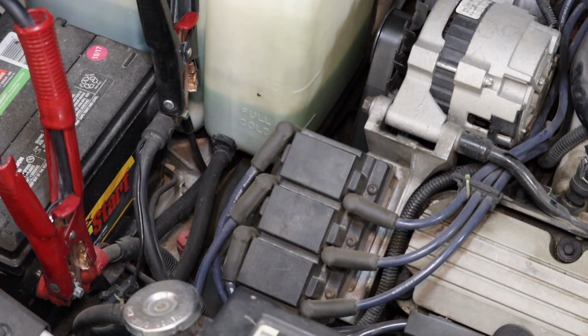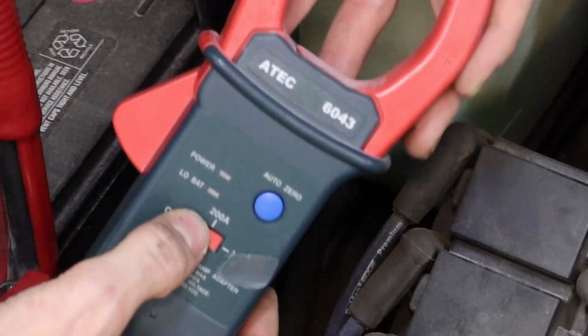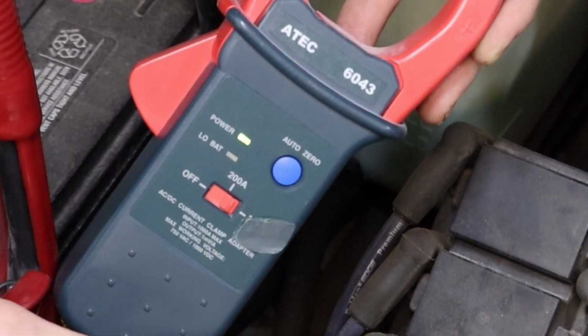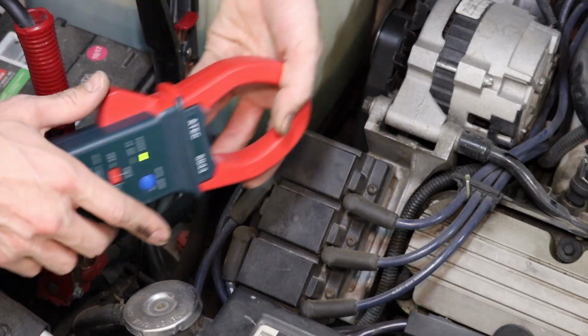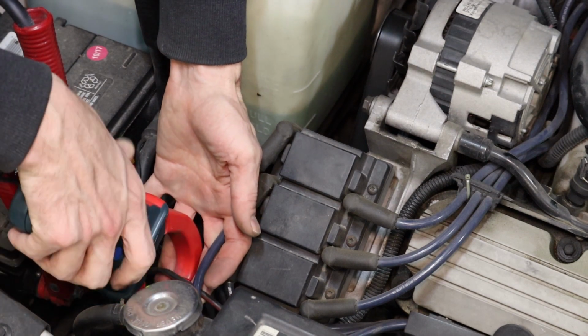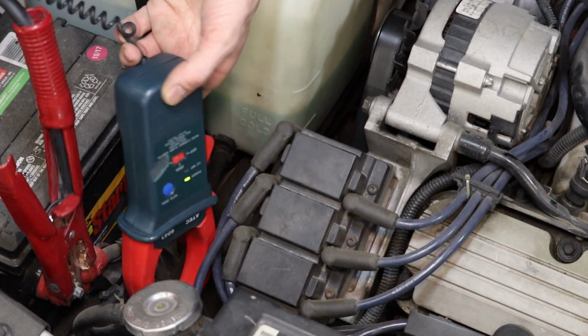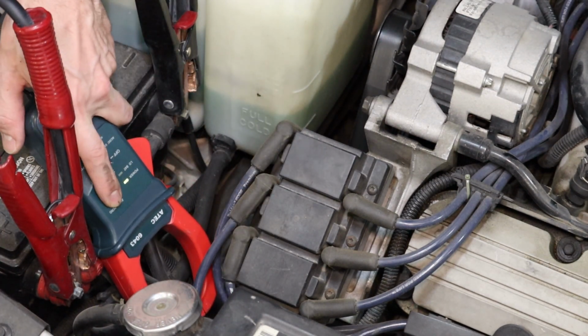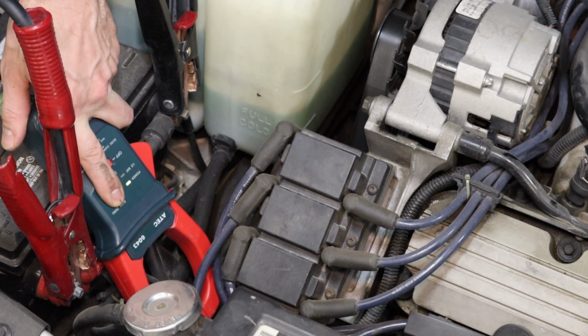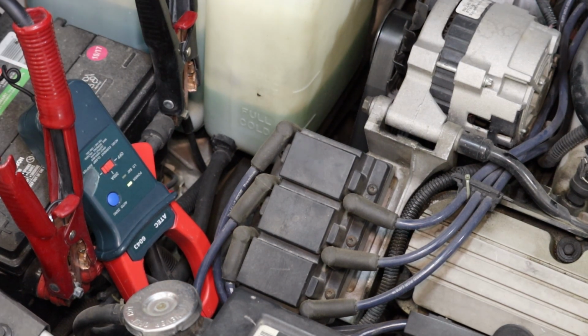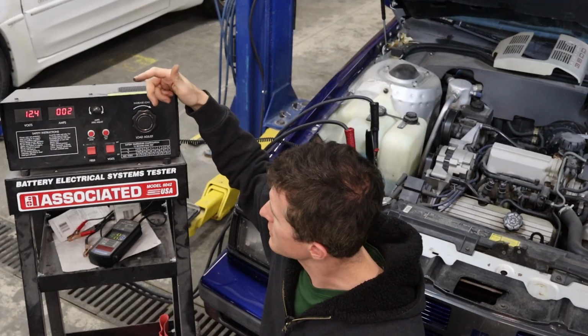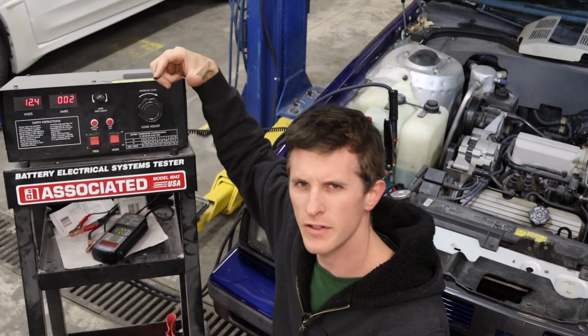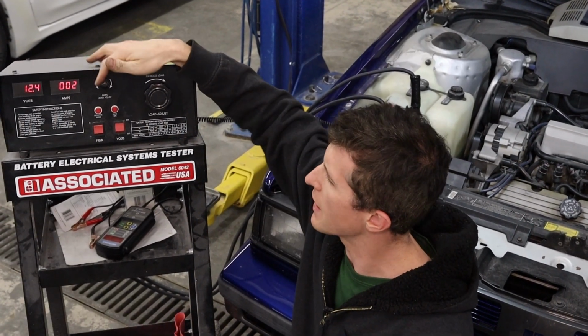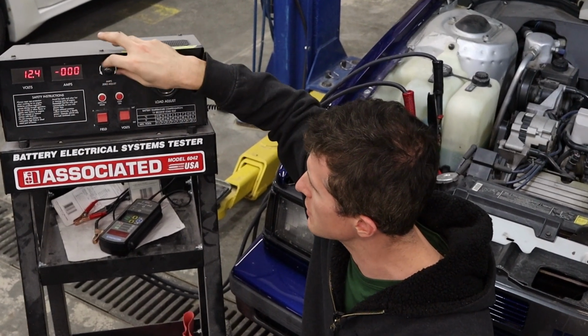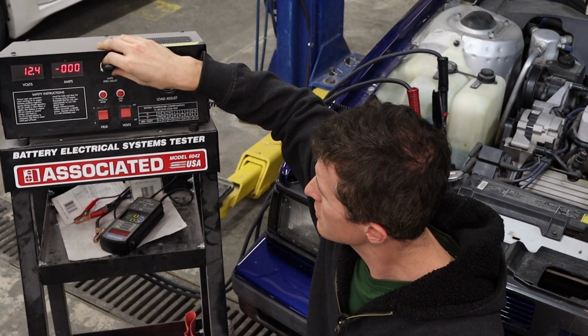So what we do is grab the amp probe, slide the switch all the way over to 1,000 amps, and clamp that around, making sure it doesn't get caught in the drive belt. We'll push the blue auto zero button, just like we did before in the battery testing. Now that we've zeroed the probe, and the probe is completely analog, we'll rotate the amps zero adjust to where it says 0.